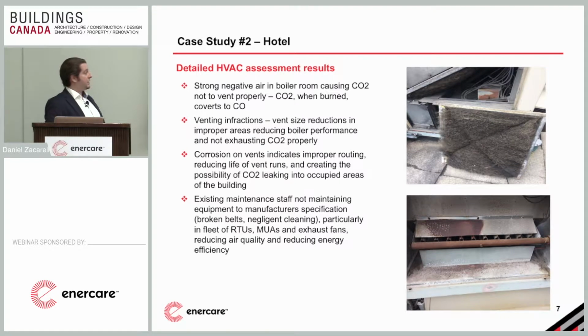But the vent sizing is important for allowing the flue to naturally draft out. Without that natural draft, it creates issues, for example, like that one before, where CO2 comes back into the room. And then just in general, similar to the other properties, you've got pictures here of filters that look like they haven't been changed in years. Burners here, for example, because they haven't been cleaned in a long time, are starting to rust and combust on themselves. I'm sure if you pulled one of those burners out, they may even start to disintegrate in your hands as they pull out from the age of that unit.